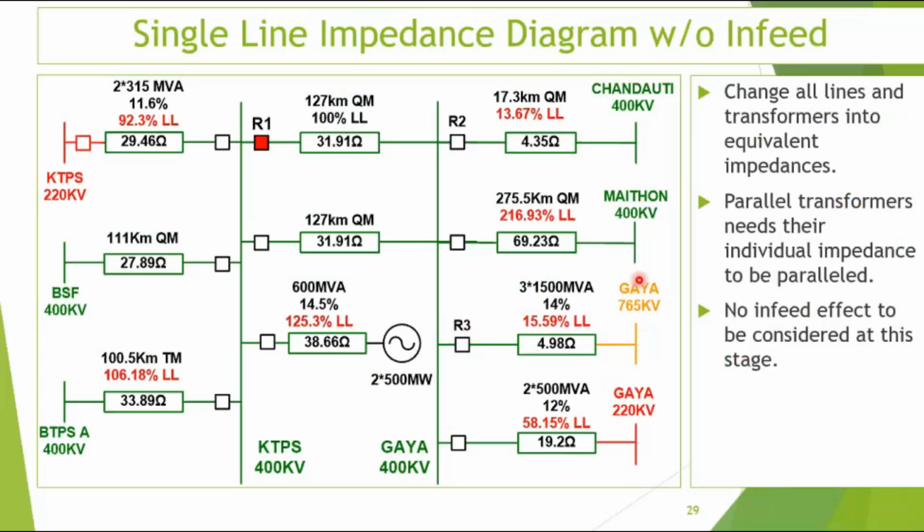There are other conditions, of course. Second level, this zone 3, what we talked about, it should back up the primary part of this, that one I am talking about. Okay. So these are the two impedances that we have to be very careful about. This 4.35 and 4.98. These are the cases where overreach can occur.